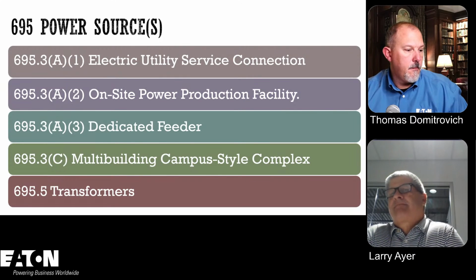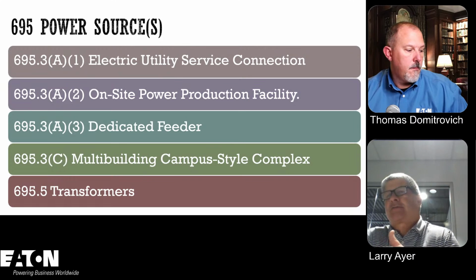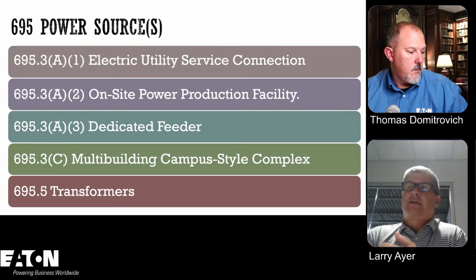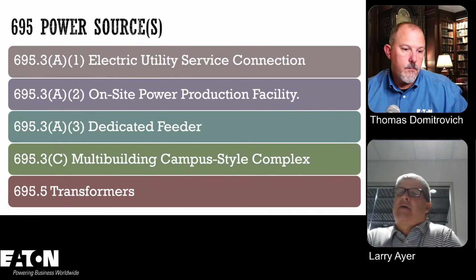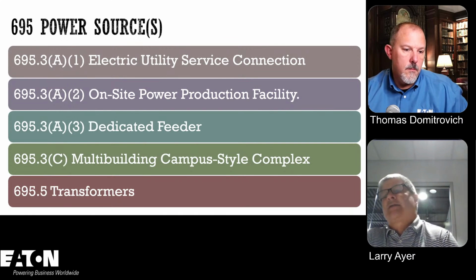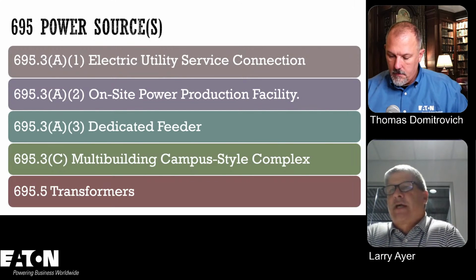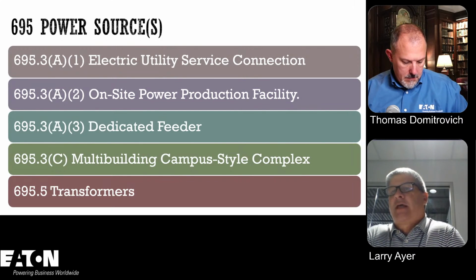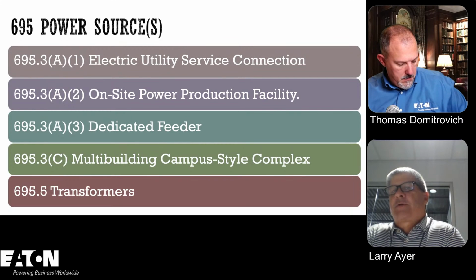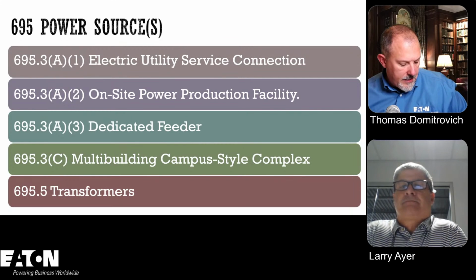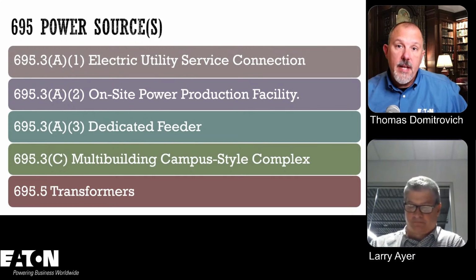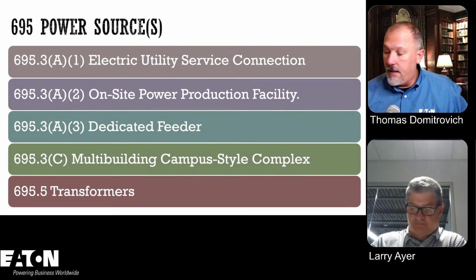I think that putting in a 13.2 step down transformer, there's a lot of stuff that's going to play there. That's why someone might say, I'm going to try the diesel engine fire pump. But I've seen it different ways. And this comes back to the 90.4 issue. I think you need to work with the AHJ to come up with something that serves everybody's purpose. Yeah, and Al pointed out that 695.5 addresses that. And I know you can get medium voltage fire pump controllers too. So you can get a medium voltage fire pump and controllers associated with that.